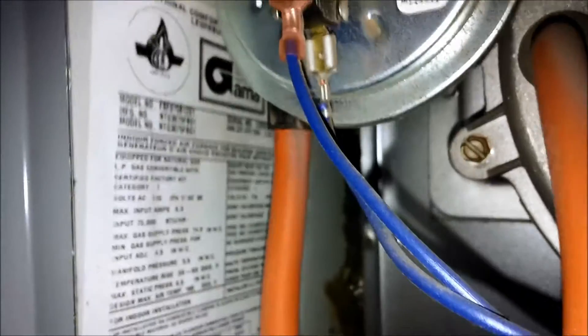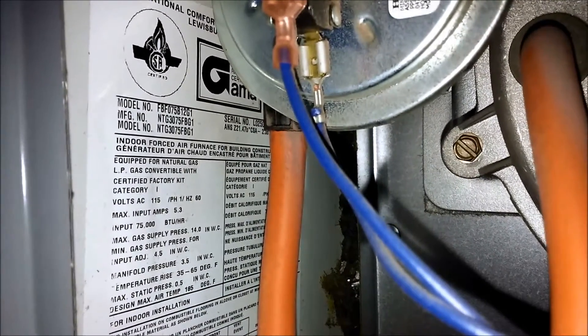So this is NTG 3075 from 2002, Comfort Maker. Got to check the heat exchangers. We just got done with that one with the cracked heat exchanger. This was a call for a furnace making noise — it had a bad inducer motor. That's really all it had wrong with it. The furnace was in decent condition, other than the cracked heat exchanger.